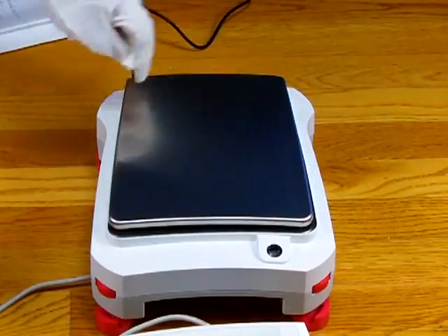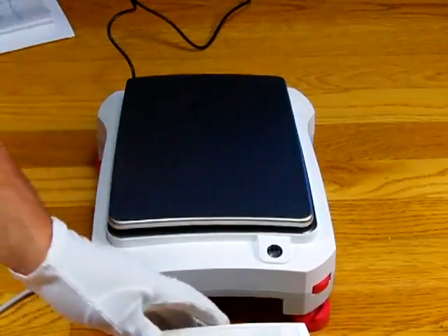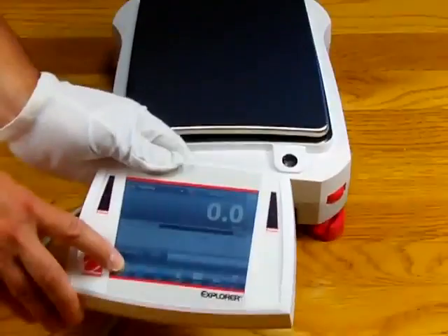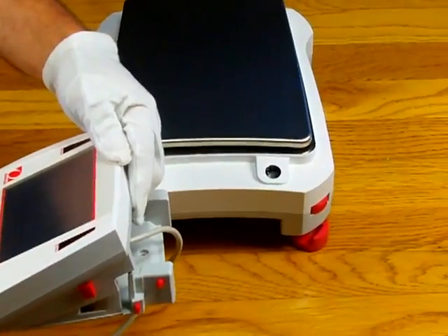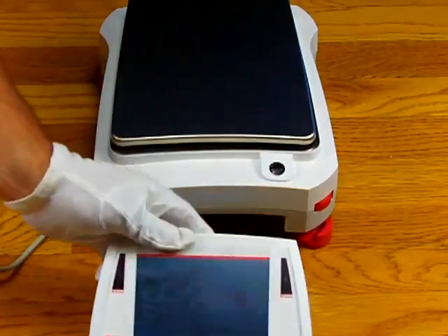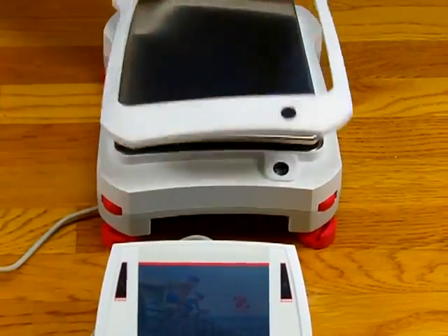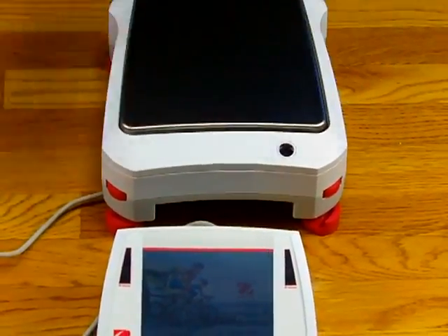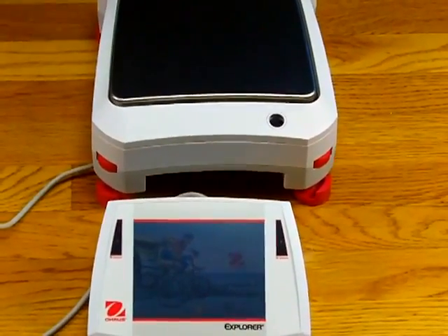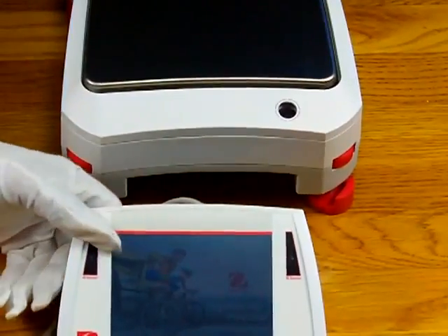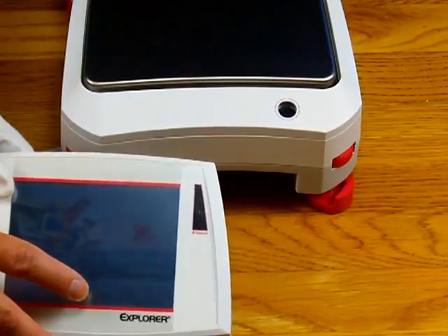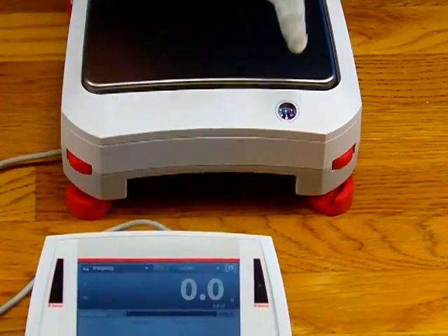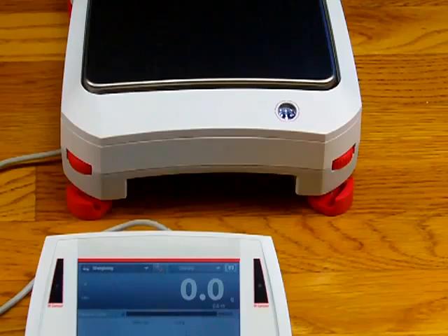Another feature on the balance is the SmartBubble indicator. I'm going to shut down the balance and put it into standby mode, confirming yes. Now the balance is in standby mode. When this balance powers up, you'll notice the SmartBubble indicator, a nice feature on the Ohaus. It will flash and light up to give you an idea if the balance is level or not. When I press the button to start the balance out of standby mode, it's telling the operator to level the balance, and there's an intuitive menu to help with that.